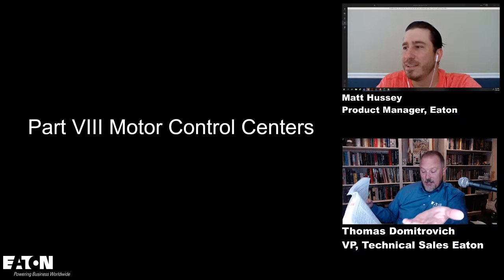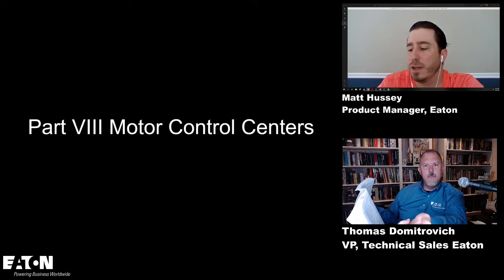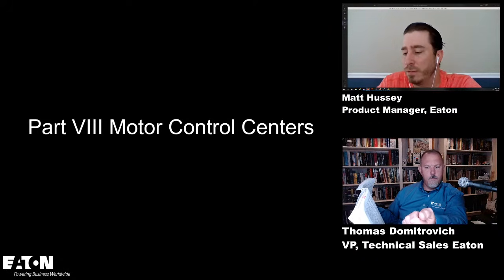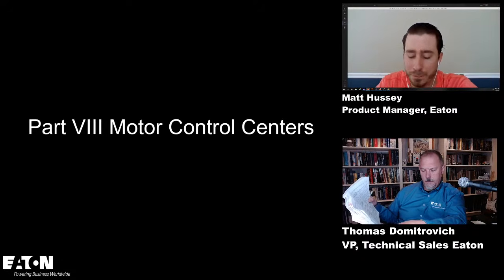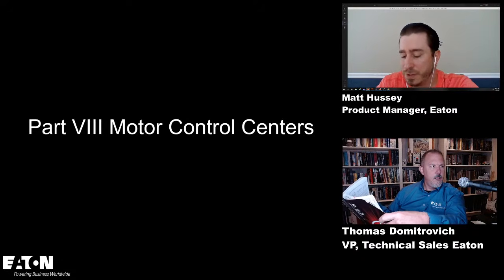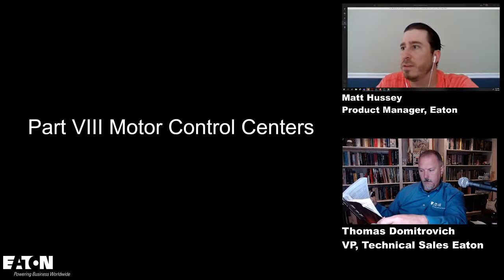You do have your general requirements. It covers motor control centers installed for the control of motors, lighting, and power circuits. Lighting? What's up with that, Matt? Yeah, we can use something like a full voltage contactor for lighting loads. Maybe you've got a parking lot or a facility, and you might have a contactor that switches on once it gets dark out.